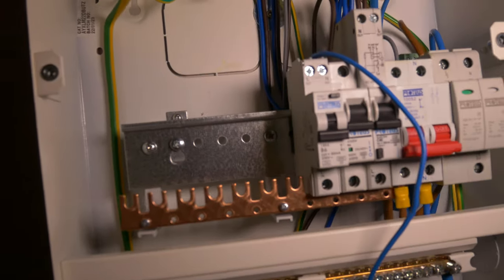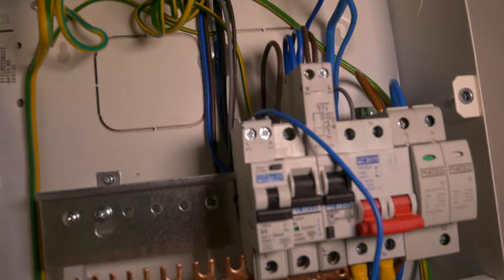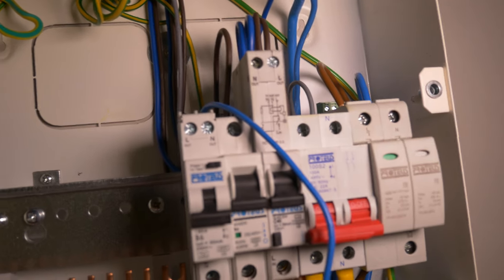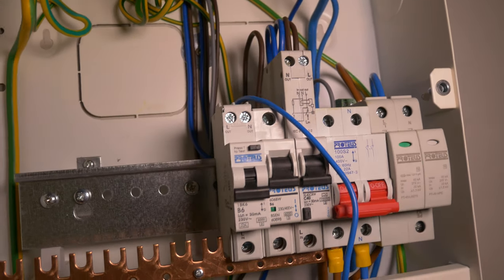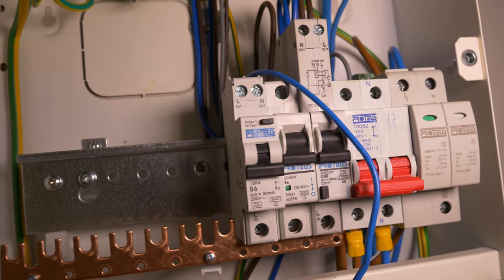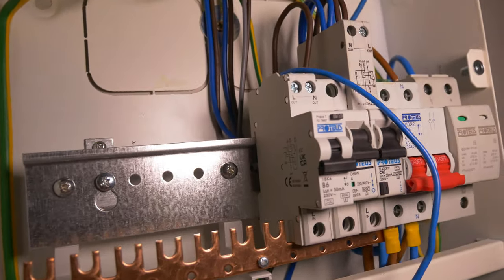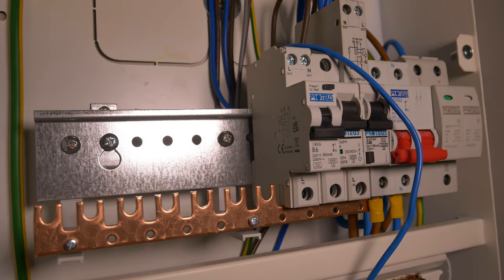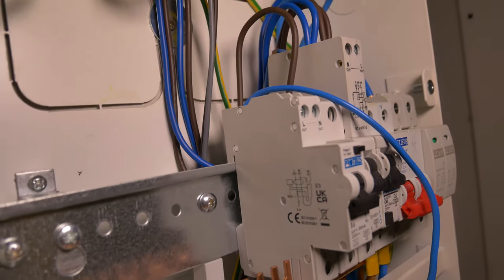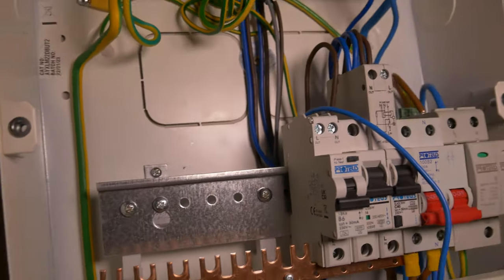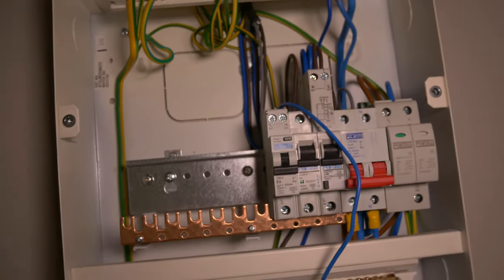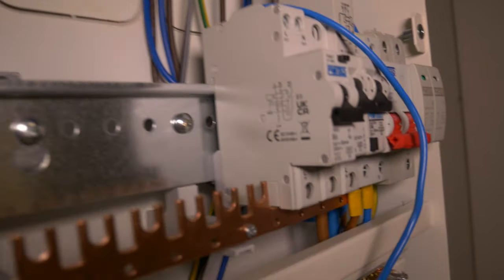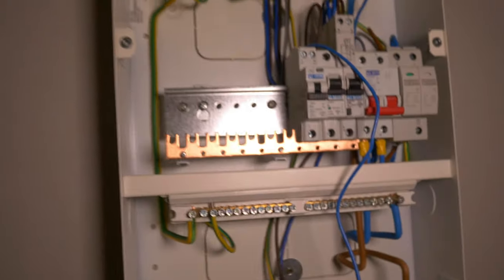You see there, we've got the tall RCBO on the right. So this is one of the older varieties. That one's a 10kA version, so you typically use that in a commercial board. We've then got a normal MCB just next to it, and lastly one of the compact RCBOs that we'll have a look at in a minute and explain exactly what they do. But just to show the form factors inside this board, you can see obviously the tall RCBO is quite substantially larger, whereas the mini RCBO is pretty much the same size as the MCB, both in the way it fits onto the DIN rail and bus bar and its overall shape. So that's good to know.